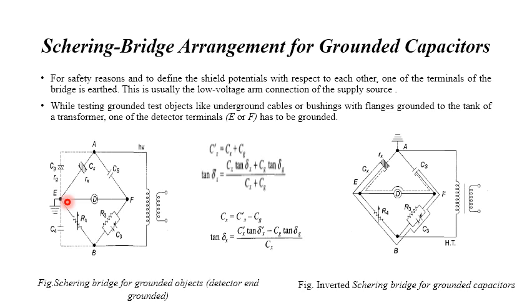So in the case of the grounded detector arrangement, the stray capacitance of the high voltage terminal, that is nothing but CG, and of the source lead etc. comes in parallel with the test object, which you can see here, CG and this CX, which come in parallel. Hence the balancing is to be done in two steps. The first step is the disconnection of the capacitance CG, and there is a measurement of tan delta. Then the test object is connected and a new balance is obtained. So there is a second balance which you can write as Cx dash is equal to Cx plus Cg.